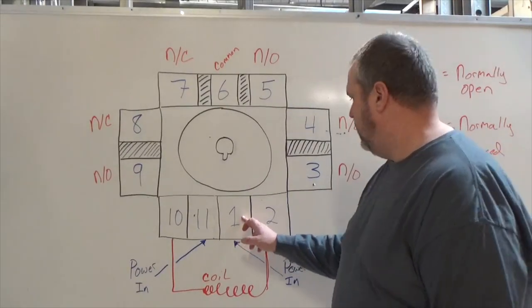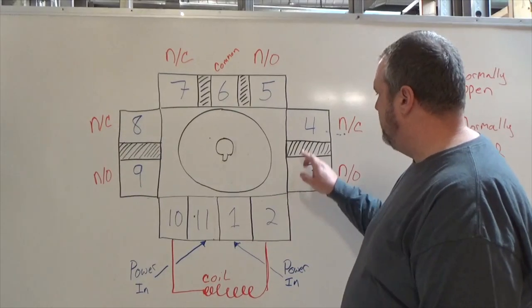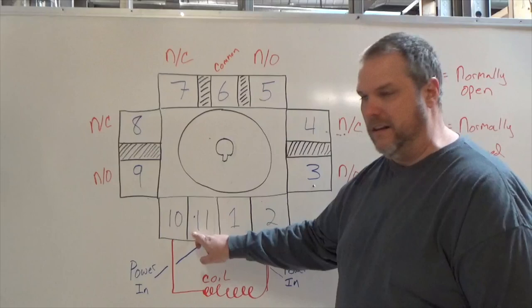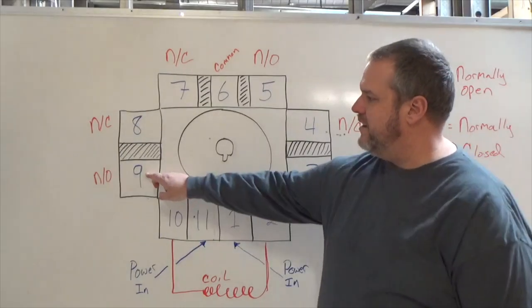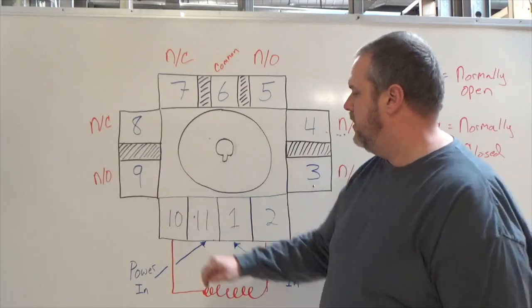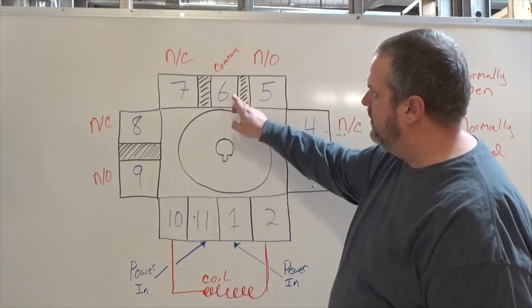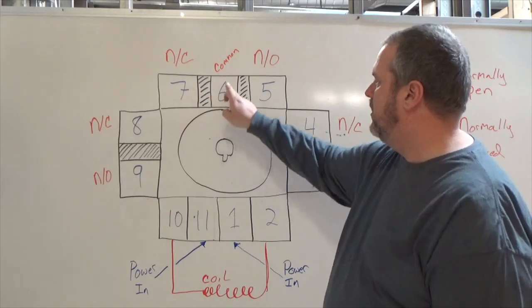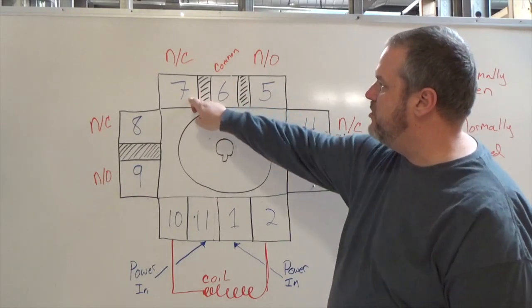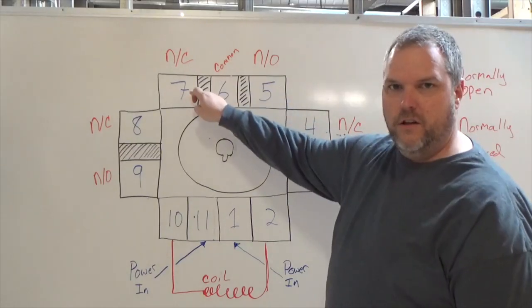Pin 1 will operate your normally open and your normally closed, pins 3 and 4. Your 11 will operate your 8 and 9, normally closed and normally open. Now typically, 5, 6, 7, your 6 would be your common and you would use your 5 and your 7 as your normally open and normally closed.